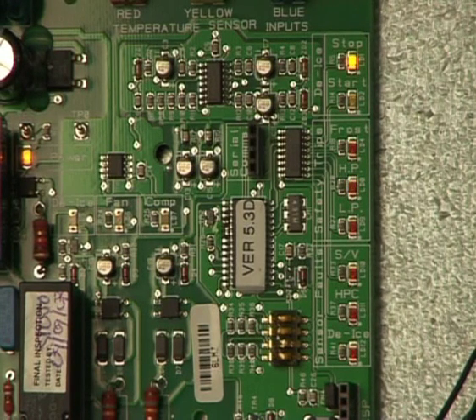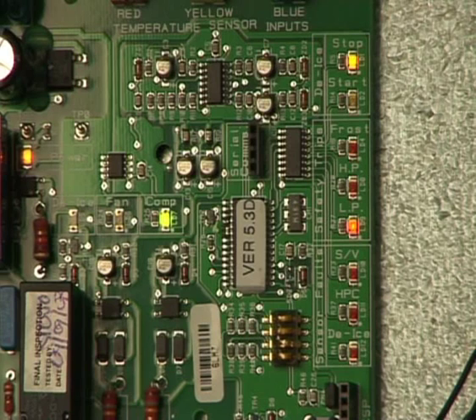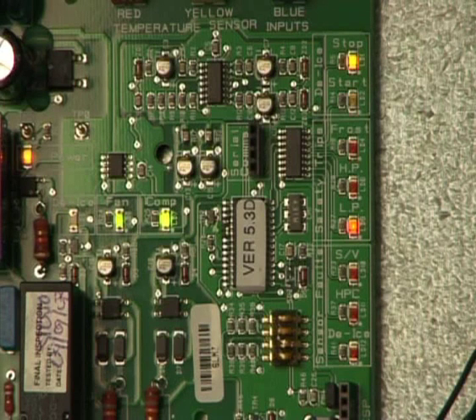High pressure protection is activated via the traditional type high pressure switch. If the high pressure switch should open circuit, the compressor will shut down for 3 minutes. Confirmation of a HP trip is via the HP LED. As with the Frost Protect feature, repeated consecutive trips will result in the compressor locking out until power is removed and restored to the unit. Low pressure protection is only applicable if an LP switch is fitted. Larger commercial and some custom-built units are the only units likely to have an optional LP switch fitted. An open circuit LP switch will shut the compressor down for 3 minutes and activate the LP LED.